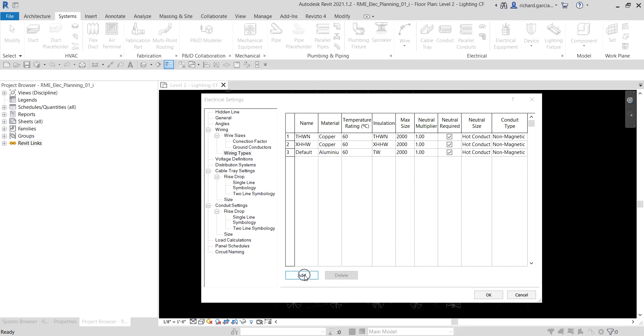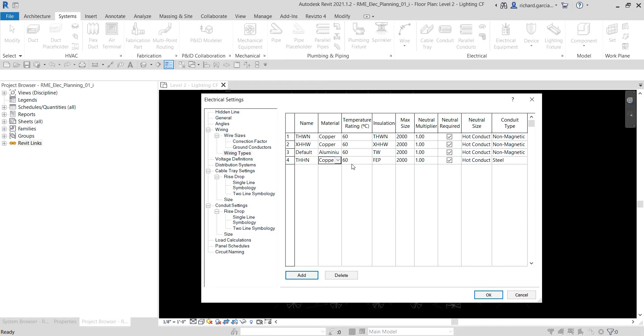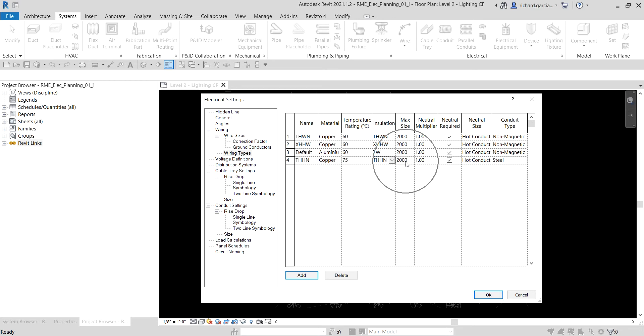Let's create a new wire type by clicking Add. I'll specify the name as THHN wire, set the material to Copper, and the temperature rating to 75. For the insulation I'll use THHN, maximum size 2000, neutral multiplier 1.0, and neutral required. That's how you add a new wiring type to your project.